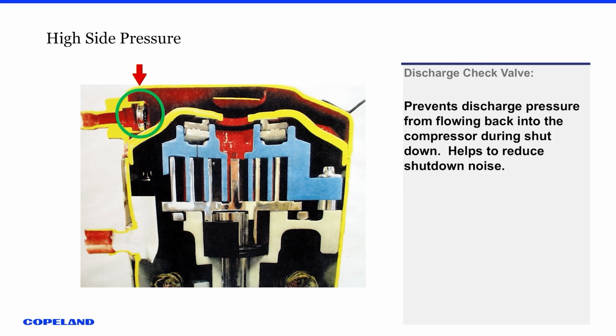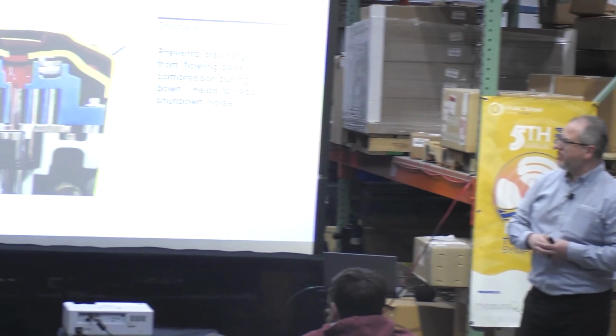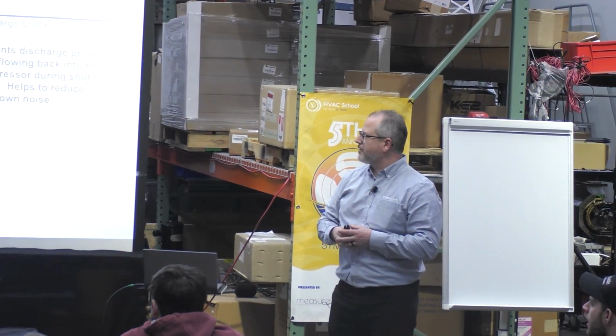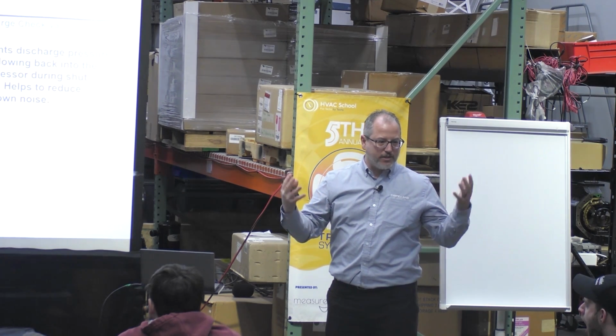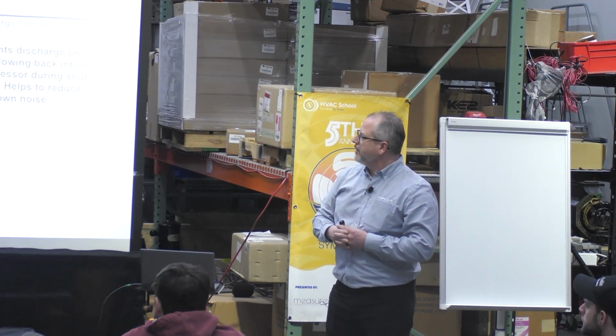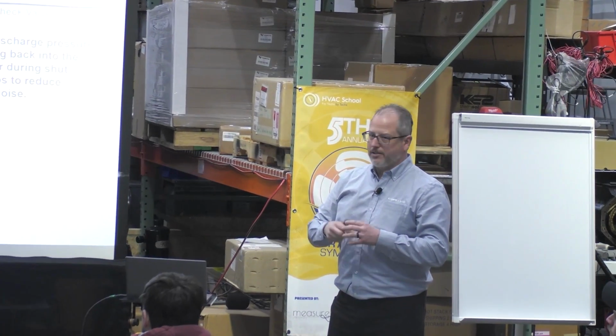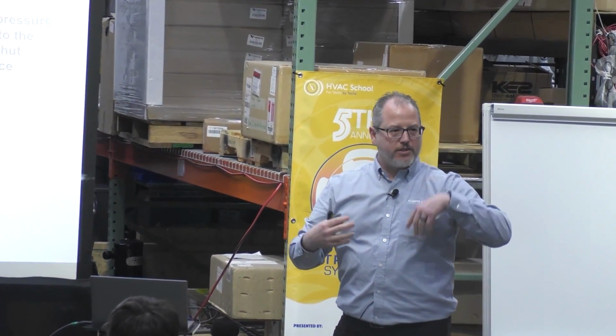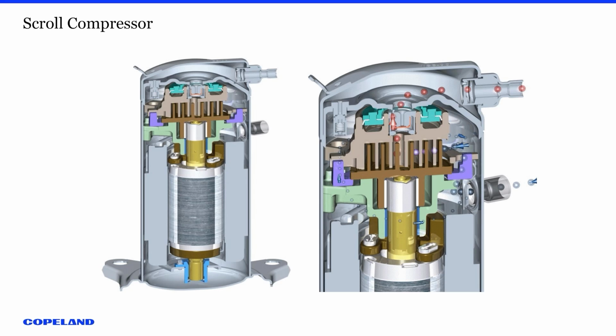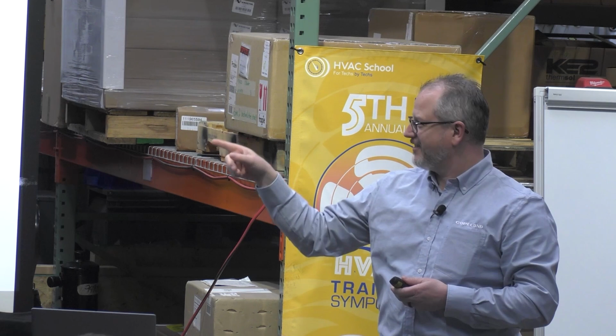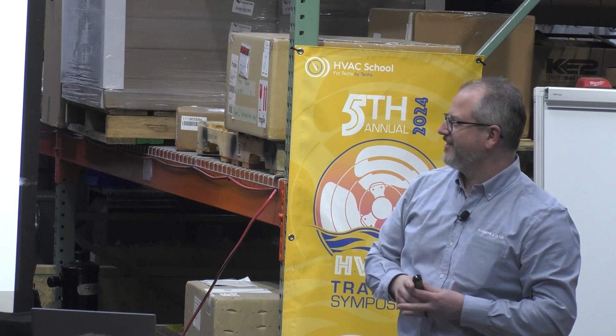Other compressors have check valves in different spots also, to prevent, when we have a larger compressor with a lot of capacity and discharge gas, that high pressure from going into the low pressure and turning our scroll set the wrong way. So this is a little picture of how it works. And if you guys didn't know, we even put little arrows so the refrigerant knows where to go. So you guys probably didn't know that, did you?